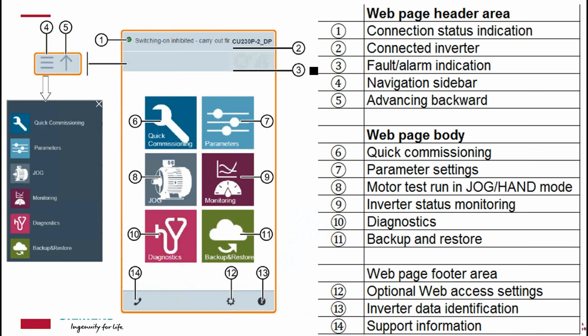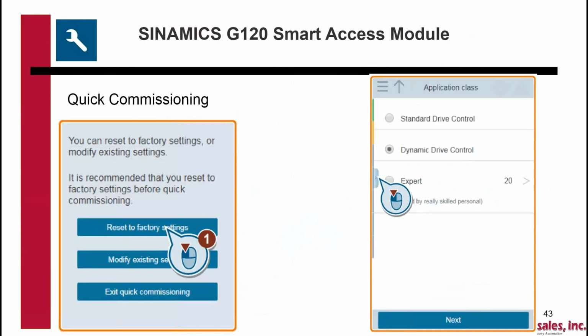Here's what the web page looks like on the G120, very much like the V20, with the same menu structure: quick commissioning, parameters, jog, monitoring, diagnostics, and backup and restore. We're going to go through quick commissioning on the G120 in the PowerPoint to show some differences between it and the V20. There are a lot more choices here. So quick commissioning, and then here's your selection: reset to factory settings, modify existing, or exit quick commissioning.